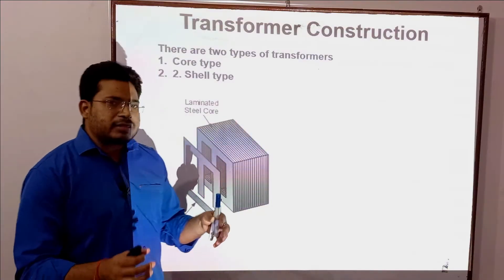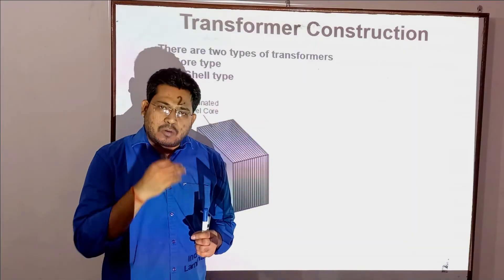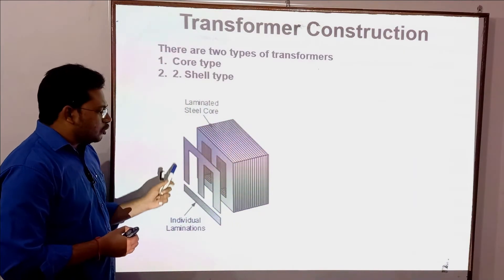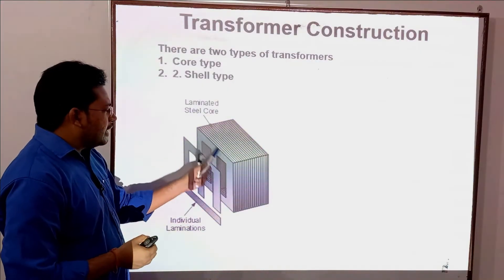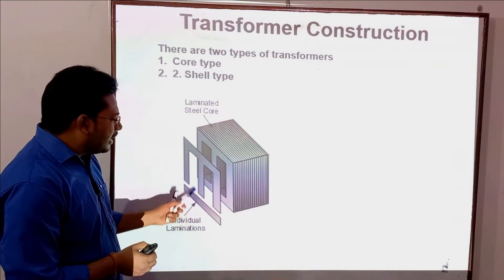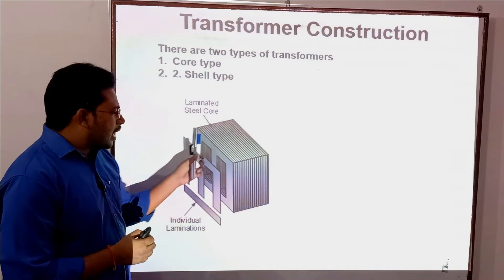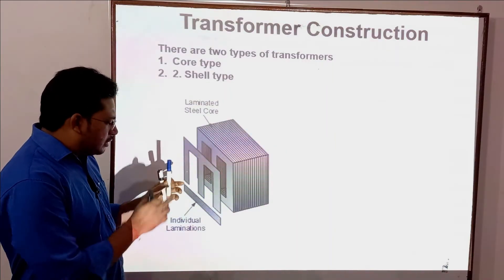The transformer core is not a solid block of material. To construct the core, we use thin laminated sheets stacked together. The core is built up as a stack of thin silicon steel laminations, typically 0.35 mm thick, creating a laminated core structure.